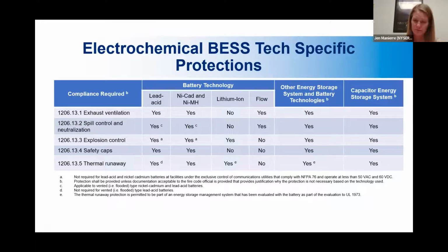And that's because, like I mentioned in the previous slide, lithium ion batteries do not off gas as part of their normal operation. They would only off gas if something was going wrong. So they don't need just normal exhaust ventilation going all the time like lead acid would, for example, that are just off gassing constantly as part of how they function.